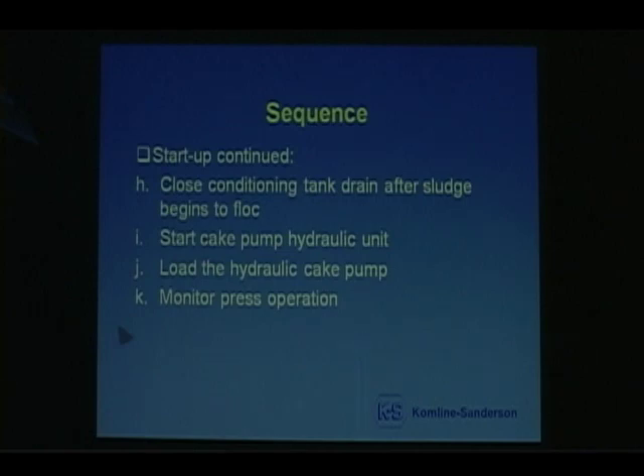And then once you start discharging into the cake hopper, you will take it off bypass and go into what they call load. You will start loading the cake pump. And that will turn on the two screws and start the rams pumping. Then you can monitor press operations, making minor changes to the belt speeds, the sludge pump flow rate, and the polymer flow rate, and possibly the belt tension.